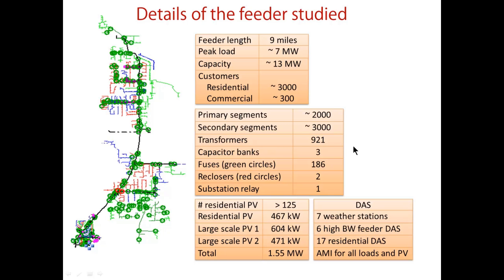And in this base feeder, we have added a high PV penetration. For the residential rooftop PV, there are about 125 systems, which total about 467 kilowatt. These are 2 to 4 kilowatt systems. And in addition, there are also 2 large-scale PV systems, one at the Dhoni Park rated about 600 kilowatt, and another one on a school rated at about 470 kilowatt. So on a feeder of less than 7 megawatt load, we have a PV of about 1.5 megawatt, and at light loads you have seen penetrations as high as 40%.